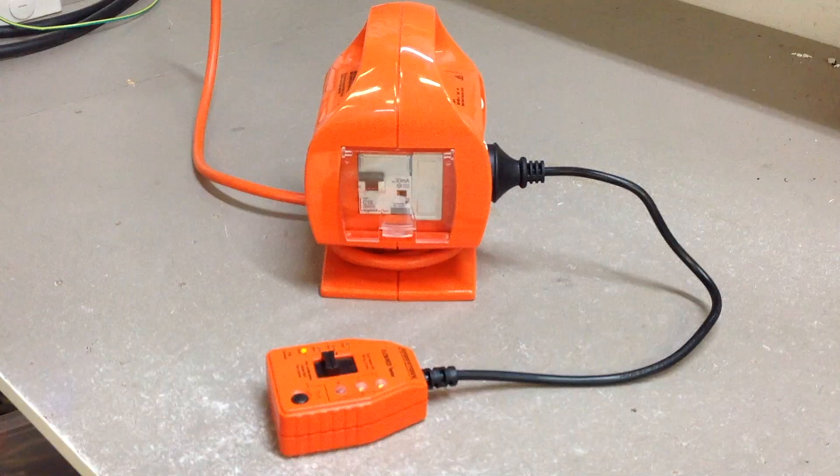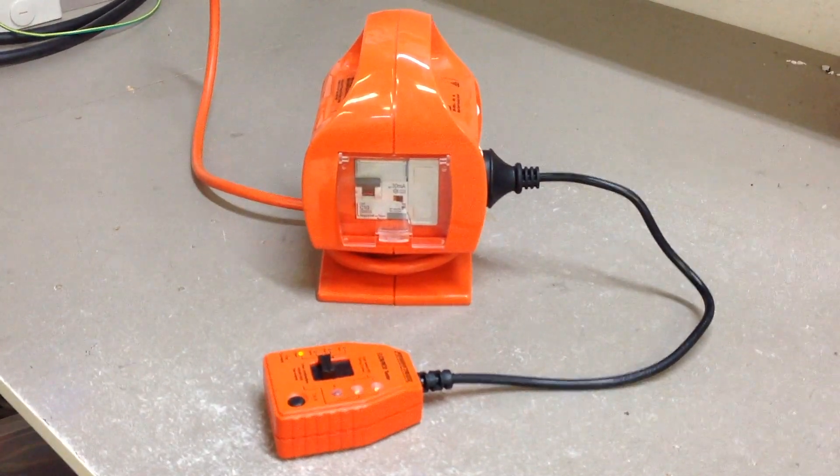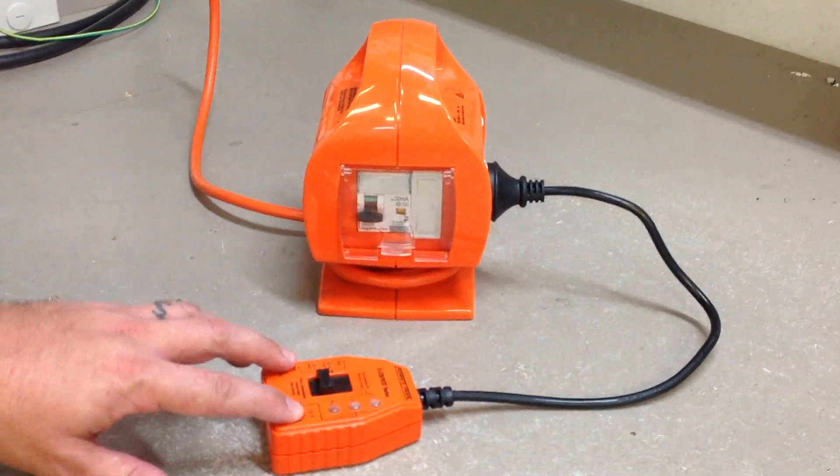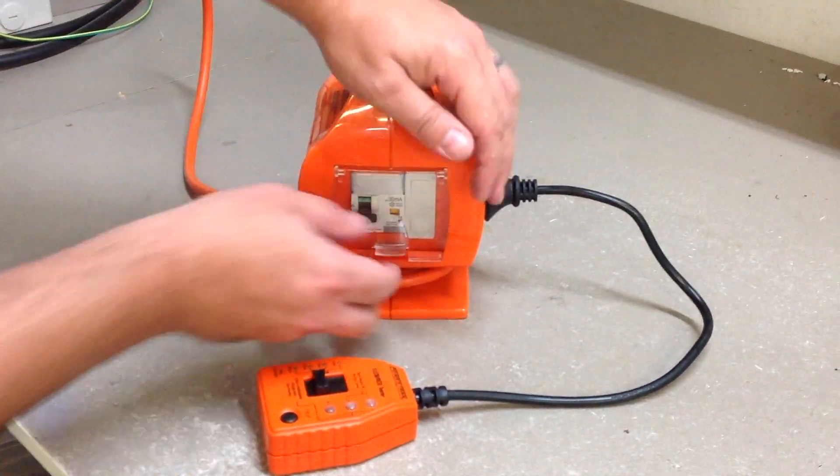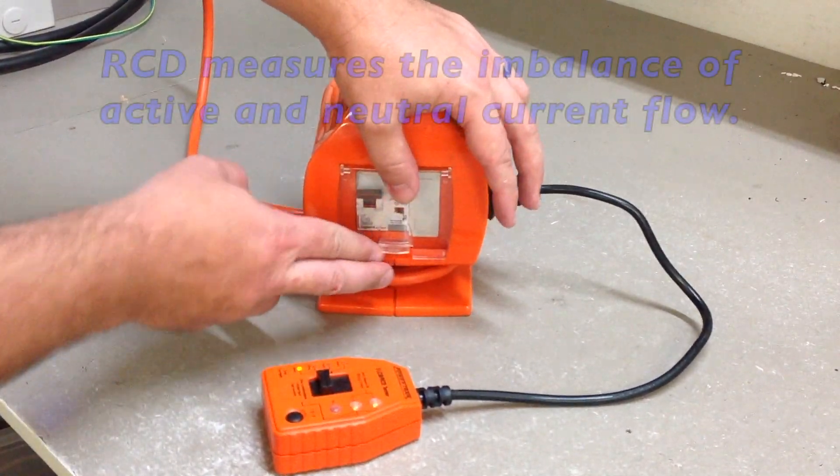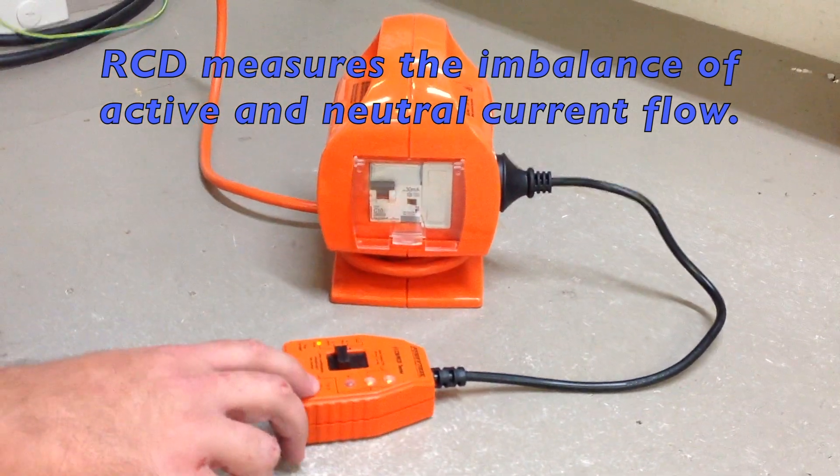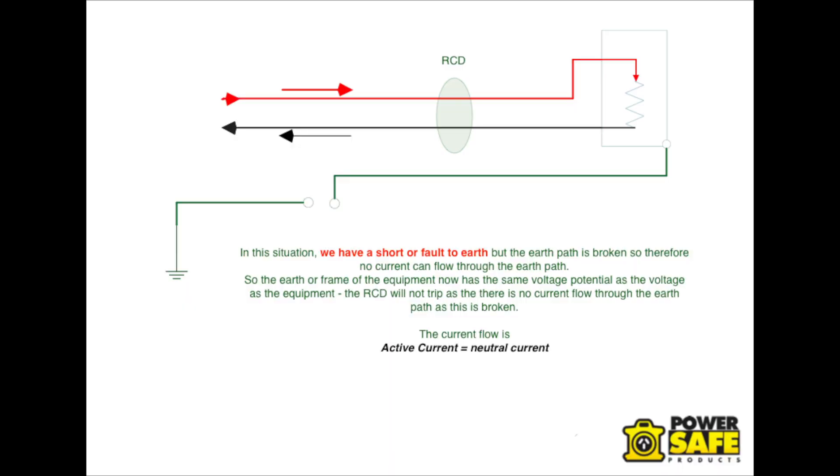This is how any RCD would operate that is fitted to a power outlet or inside the main electrical board. It measures the imbalance of active and neutral. For the imbalance to occur, there needs to be an earth path circuit that the electricity can flow through.